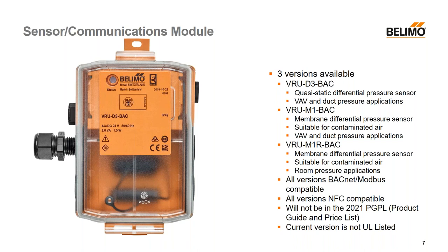Finally, we have the VRU-M1R-BAC, which also uses a membrane differential pressure sensor — actually the same sensor as the M1 — except it has been calibrated to plus or minus 75 Pascals. That makes it suitable for room pressure applications. If you're trying to create slightly positive or slightly negative pressure, this sensor will control much better than any of the others in that range.